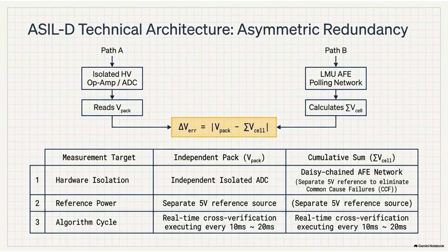Yes. And the engineering tolerance here is what is truly staggering. When that pulse propagates across the bus, every single AFE chip on every module, along with the isolated total voltage ADC on the master board, must lock in their physical voltage readings within a synchronized window of exactly 1 microsecond. 1 microsecond, let's really contextualize that. 1/1,000,000th of a second. We talked about a 50 millisecond delay earlier. A microsecond is 50,000 times faster than the latency gap we were dealing with.